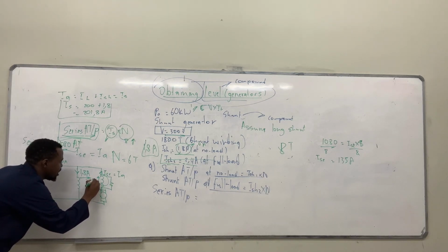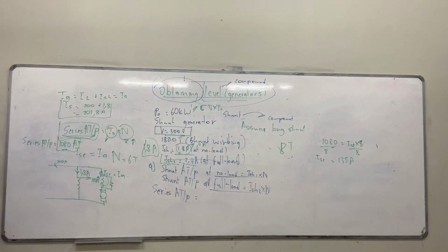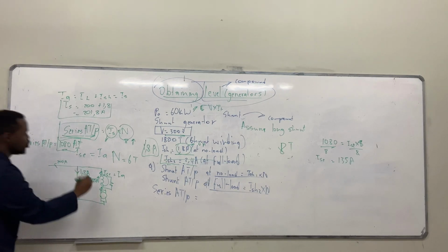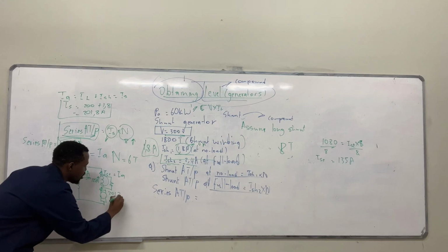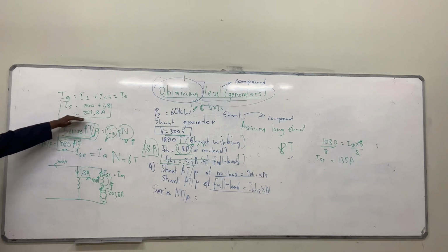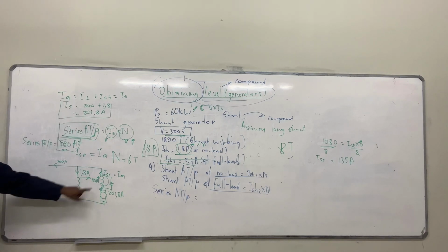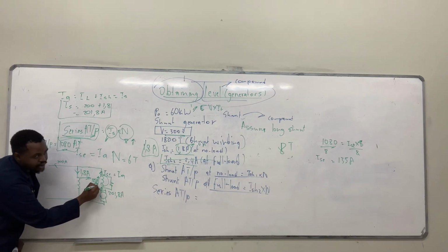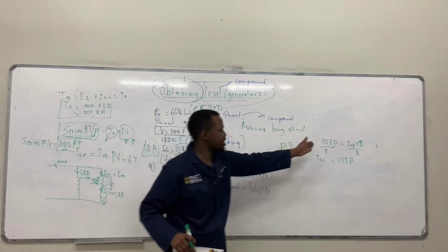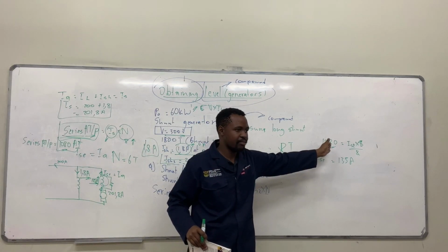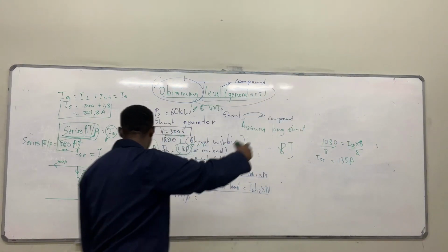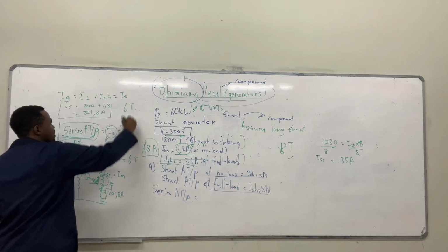135 amps? The current from the armature was 700 plus 1.8 amps. They were equal at the beginning, but now they are not equal because we want this current to be 135, so that we maintain the series ampere turns per pole without having to buy a winding with 6 turns.